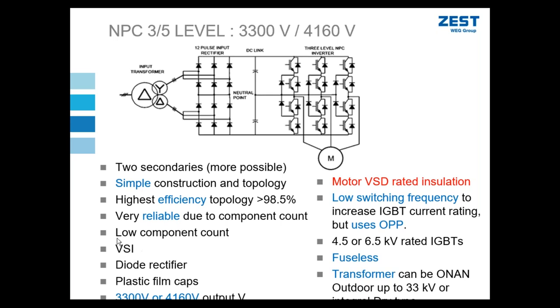It is a voltage source inverter, so it comes with all the advantages that a voltage source inverter provides. For example, very high dynamic response to a change in torque on the output of the drive. It is possible to use plastic film capacitors as opposed to using dry electrolytic type capacitors. These have a much longer design life and they do not need to be reformed after storage.